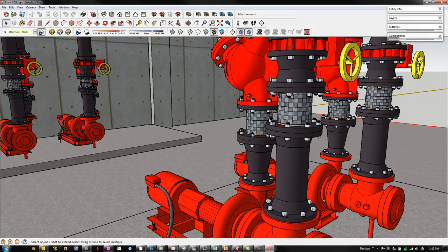But if you think about there's a disc spinning inside this part of the pump and it's flinging the water to the perimeter, well, the water probably just about has to come in this way and then go out this pipe here, since this pipe's attached to the perimeter of the housing where the disc would be. So that's another way to figure out which way the water's going. And what I like about that personally is it's based on the physics of how a pump runs. And in fact, even if you spin a centrifugal impeller backwards, it still flows water in the same direction. It's just not very efficient at it, because again, it's just a disc flinging water.